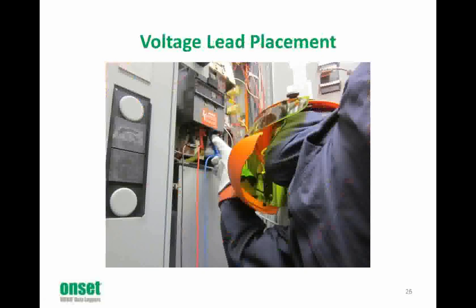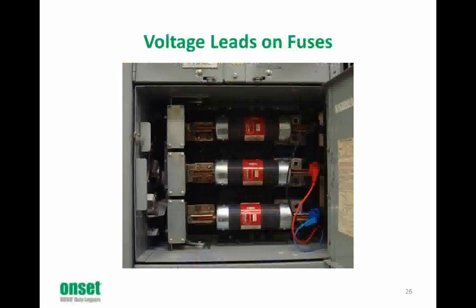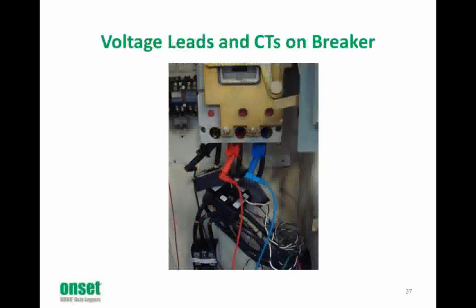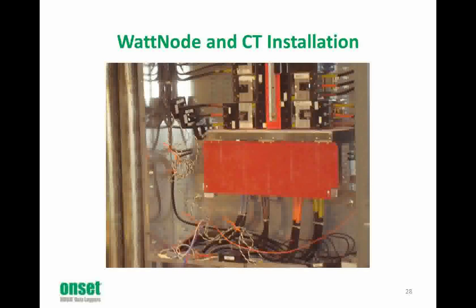The next couple slides will give us examples on where to place voltage leads. Here are voltage leads on fuses in electrical switchgear. Here are voltage leads and CTs on a circuit breaker in a motor control center. This photo shows the WattNode placed at the bottom of the enclosure and CTs on the lower left circuit breaker. The voltage leads are not yet connected to the power source.